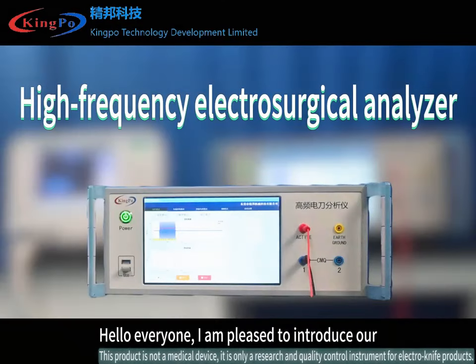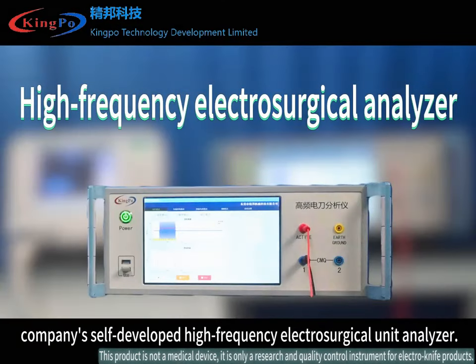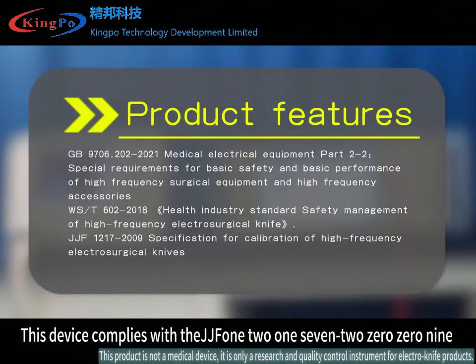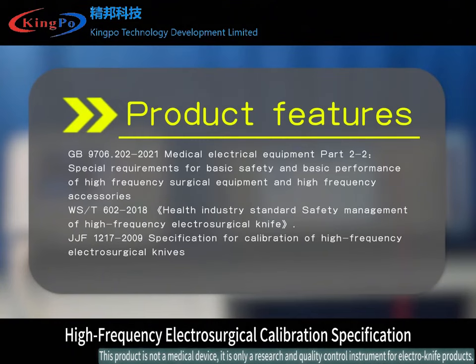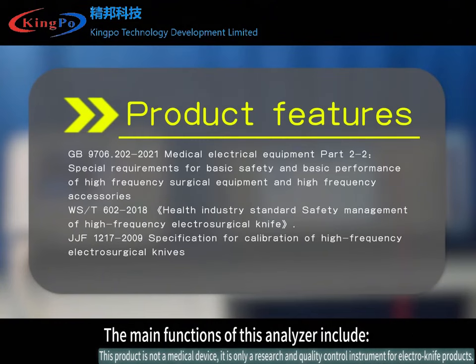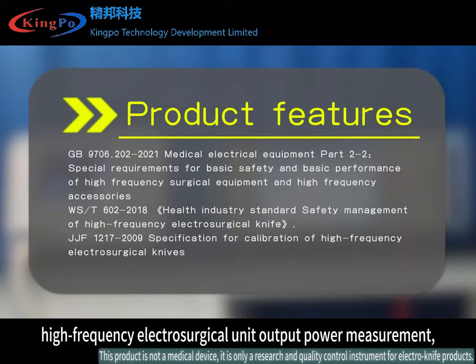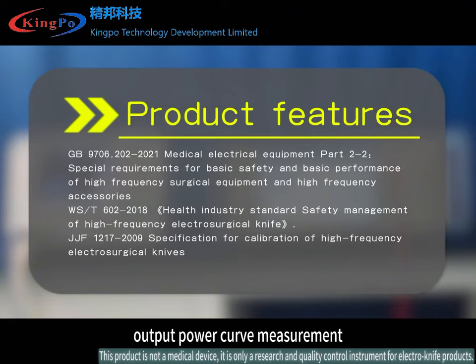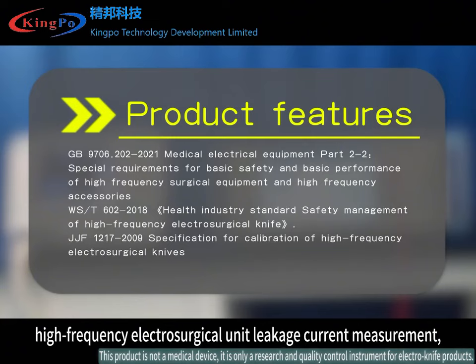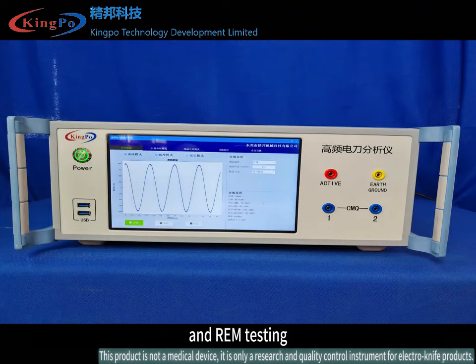Hello everyone, I am pleased to introduce our company's self-developed high-frequency electrosurgical unit analyzer. This device complies with JJF 1217-2009 high-frequency electrosurgical calibration specification. The main functions of this analyzer include high-frequency electrosurgical unit output power measurement, output power curve measurement, high-frequency electrosurgical unit leakage current measurement, and REM testing.